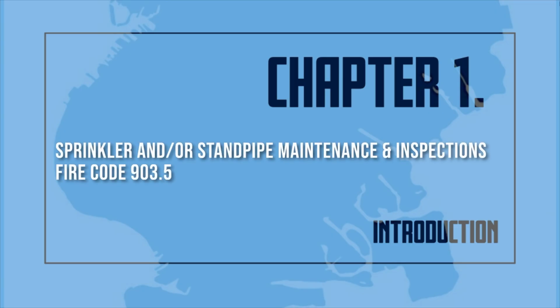Sprinkler and/or standpipe system maintenance and inspections. Fire Code 903.5.1. Automatic and non-automatic sprinkler systems shall be inspected, tested, and maintained as required by the National Fire Protection Association 25, 2002 edition, by a competent person holding a certificate of fitness employed by the owner to see that all parts of the system are in good working order and that the fire department connection or connections, if any, are ready for immediate use by the fire department. A detailed record shall be kept of each inspection for examination by any representative of the fire department.